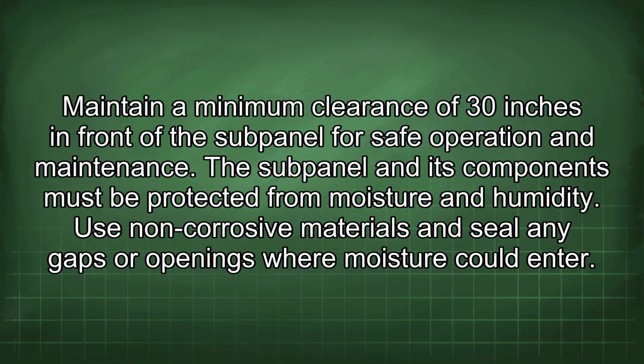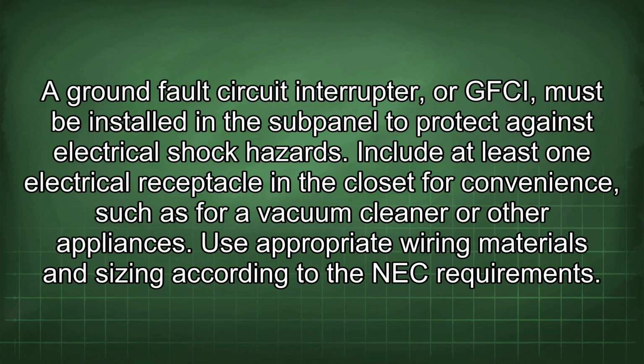The subpanel and its components must be protected from moisture and humidity. Use non-corrosive materials and seal any gaps or openings where moisture could enter. A ground fault circuit interrupter, or GFCI, must be installed in the subpanel to protect against electrical shock hazards. Include at least one electrical receptacle in the closet for convenience, such as for a vacuum cleaner or other appliances.